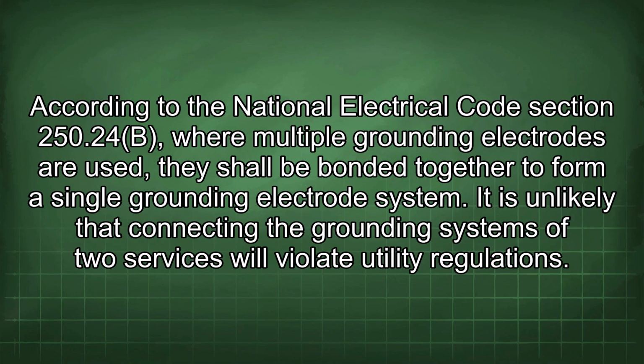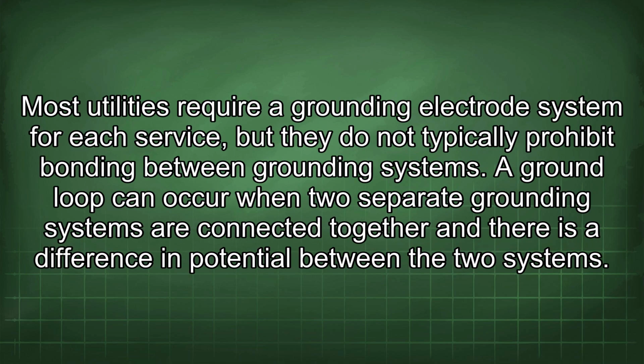According to the National Electrical Code Section 250.24(B), where multiple grounding electrodes are used, they shall be bonded together to form a single grounding electrode system. It is unlikely that connecting the grounding systems of two services will violate utility regulations. Most utilities require a grounding electrode system for each service, but they do not typically prohibit bonding between grounding systems.